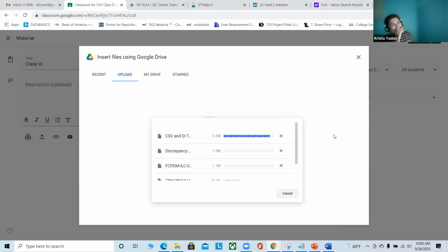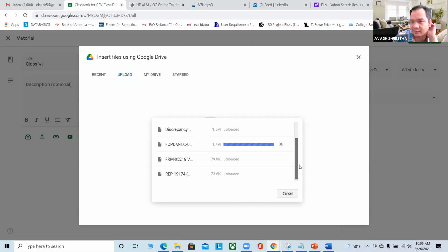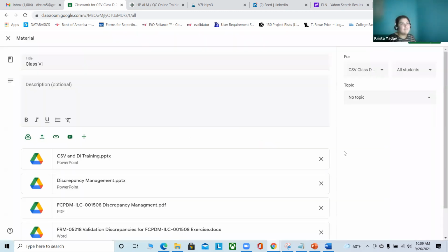Sorry, sir. It's okay, they are human too, whoever writes templates. No, at the end of our OQ and PQ template, it says something about discrepancies. Yeah, in the template you sent us, you have the discrepancy log. That's what is written on the template at the end of the IQ, OQ, PQ. I knew I'd seen it, I just didn't know what it was. If there's any discrepancy, we have to list it there.